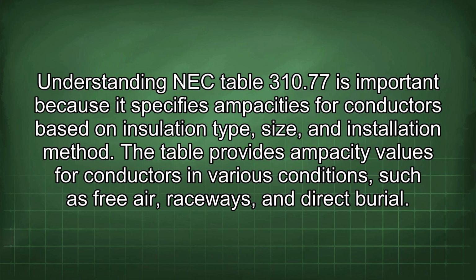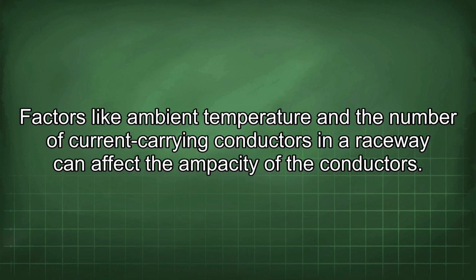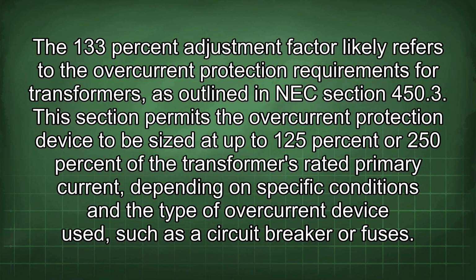method. The table provides ampacity values for conductors in various conditions, such as free air, raceways, and direct burial. Factors like ambient temperature and the number of current-carrying conductors in a raceway can affect the ampacity of the conductors. The 133% adjustment factor likely refers to the overcurrent protection requirements for transformers, as outlined in NEC section 450.3. This section permits the overcurrent protection device to be sized at up to 125% or 250% of the transformer's rated primary current, depending on specific conditions and the type of overcurrent device used, such as a circuit breaker or fuses.